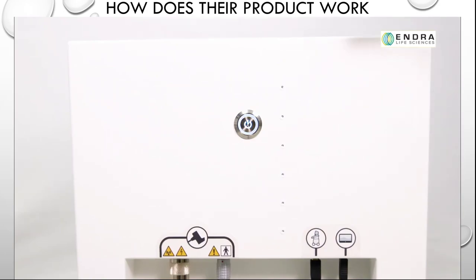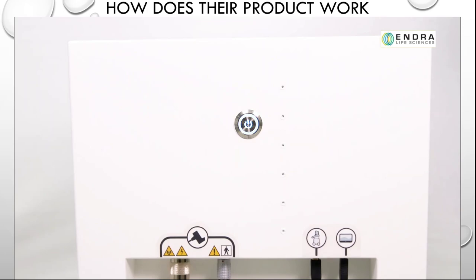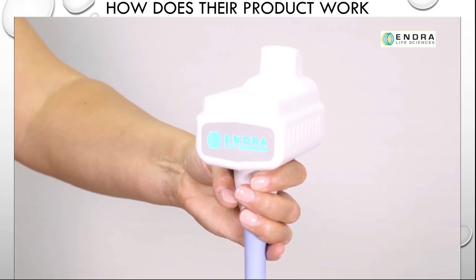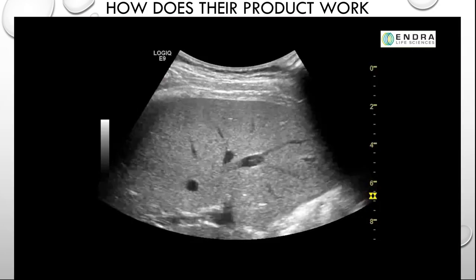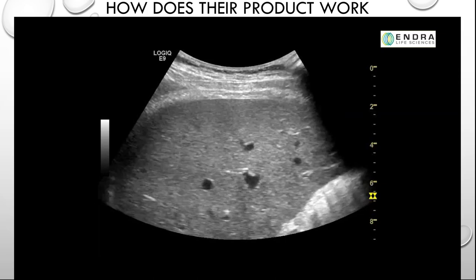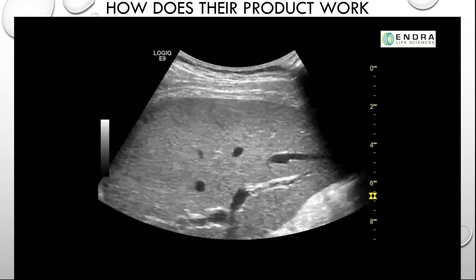To power up the TAEUS system, push the flashing white soft power switch on the front of the console. When powered up, the soft power switch turns solid white, and the status indicator on the flip probe flashes blue while it warms up. First, configure the ultrasound system for B-mode scanning. The ultrasound system is used to define a gross region of interest for the TAEUS scan and to determine the depth of the measurements to be acquired.